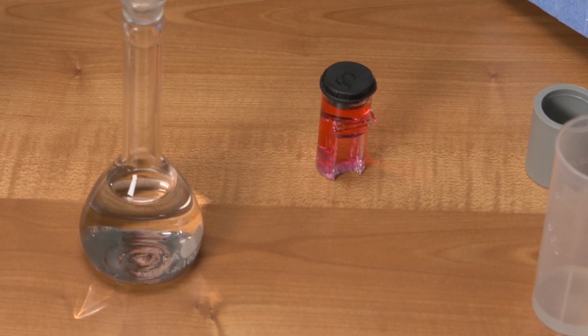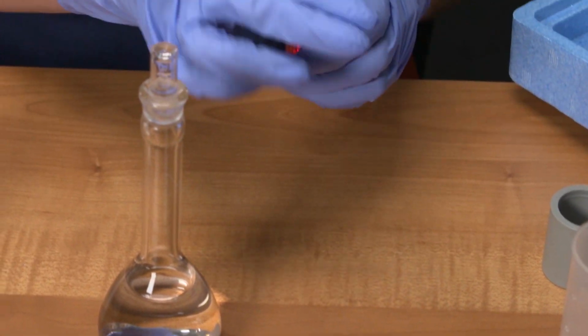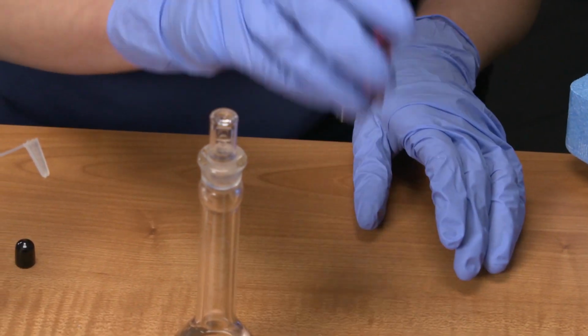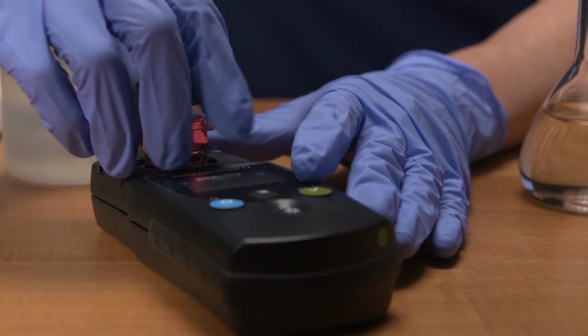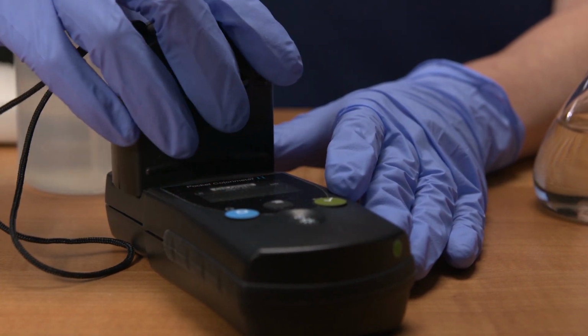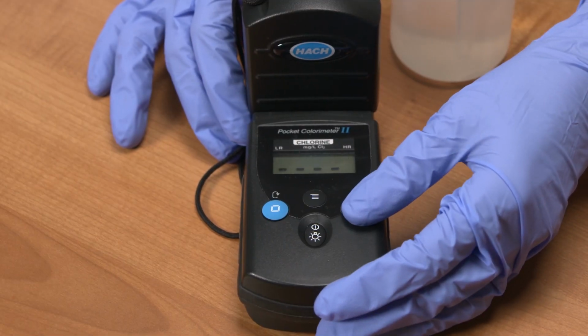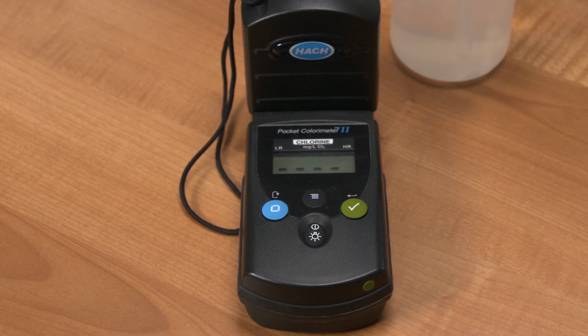If we are using total chlorine reagent, then we wait for 3 minutes for the color to develop. For free chlorine reagent, we take the reading right away. Now we take our reading and record the result. This result will be known as the concentration measured.